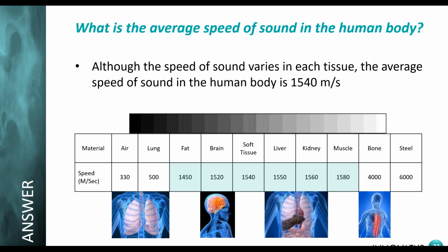And once I get that receive signal, I turn that element off, and then I go to the next element, and I do the same thing, and then I go to the next one. And you think 1,540 meters per second is really, really fast, and it is. It's kind of fast. But if you're doing it 128 times and you have to keep up a frame rate of 30 or 40 frames per second, the machine starts slowing down. So the more channels you have on an ultrasound machine, the better. But you reach the law of diminishing returns and you start actually slowing the machine down if you try and scan too many lines at once.